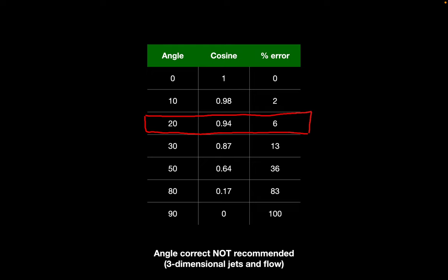Angle correction is not recommended. Many ultrasound machines have an angle correction feature where you can change the direction of the Doppler cursor line and the machine will calculate velocity based on that correction. However, textbooks do not recommend using angle corrections because these flows are often three-dimensional in nature, jets are very hard to interrogate, and you may not know which direction to apply the correction — potentially introducing further error.